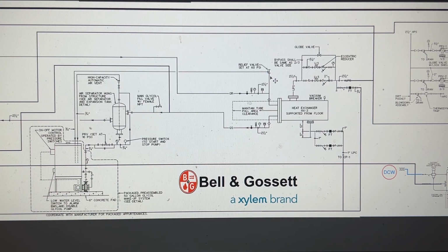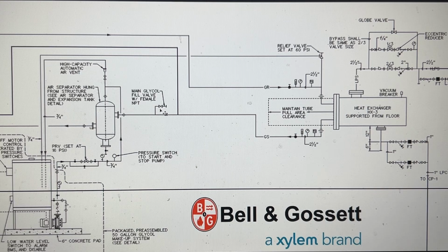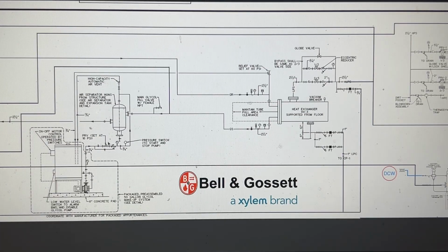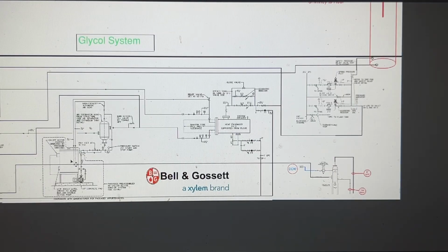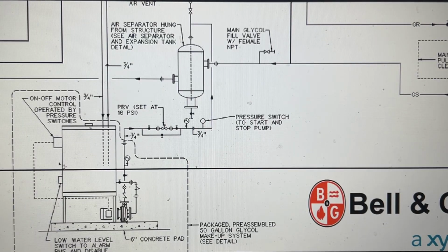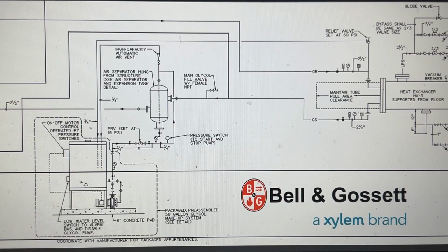So we got a relief valve if ever it overpressurizes, and an air separator, getting the air out of the system. We've got a main fill for when we fill this thing. I gotta calculate the piping lengths so that we can get a volume count for that. We got our glycol feed unit. Let's see if it says. Yeah, 50 gallon. Okay. So there will be a makeup glycol reservoir here that, in the event there should be a drop in pressure sufficient enough, will turn on and put that glycol back into the system.